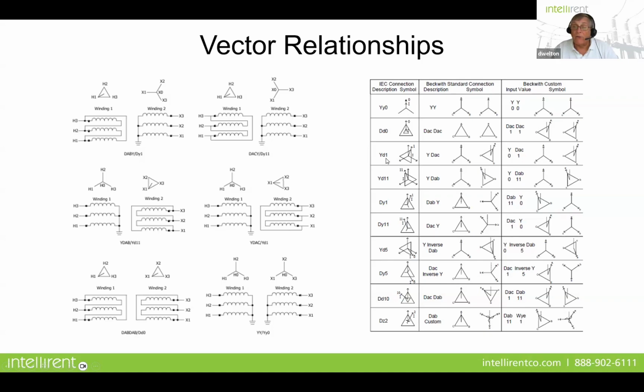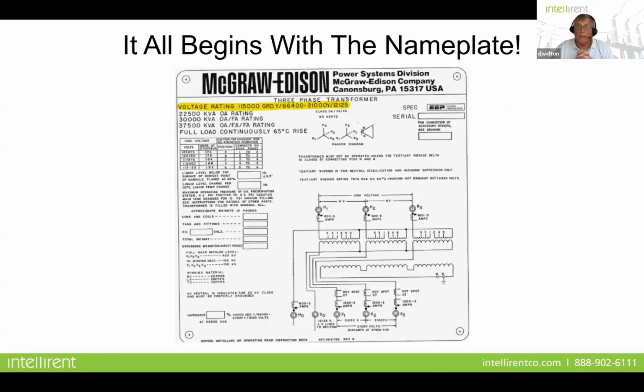When we start getting into, say, a YD1, you have a Y connected on the primary side, a delta connected on the secondary side with a 30 degrees phase shift. So it's important to really look at your transformer nameplate. And that's one of the points that I want to make out.